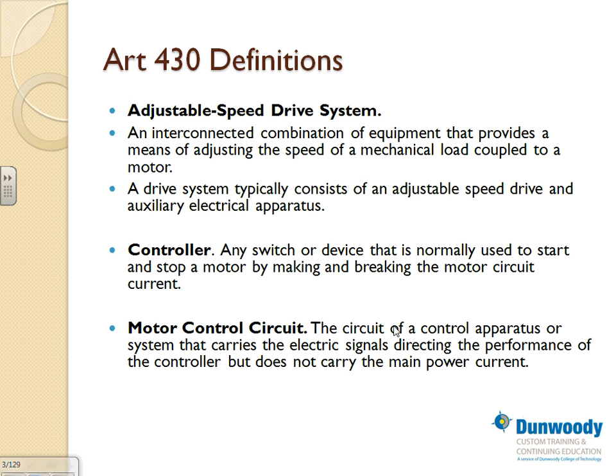So what's the advantage of an MCC? As I said, it's expensive. The drawback of having an MCC is that it's more expensive than throwing a bunch of magnetic starters on the wall with a disconnect and controlling the process. What's the advantage? You have all your control in one place, all bussed together really nicely. You have a control line in the MCC that you can use to control all these VFDs in a much easier, better way than if they were scattered all over a wall in your building.